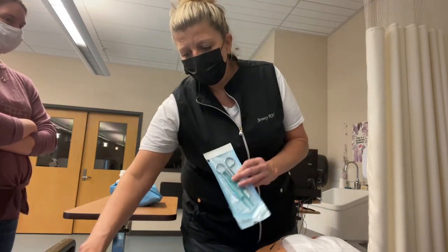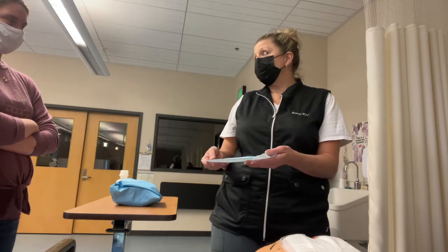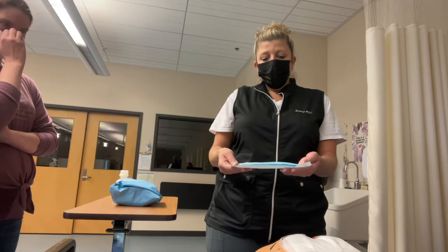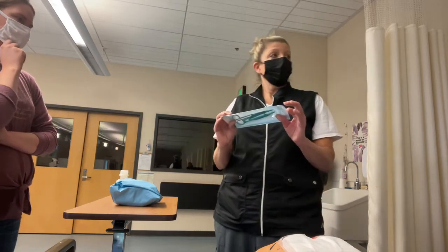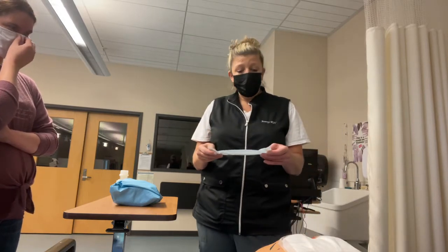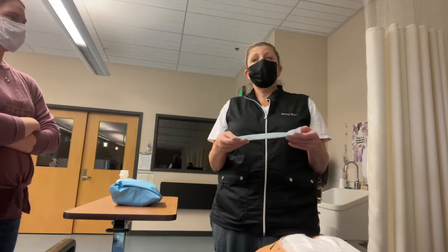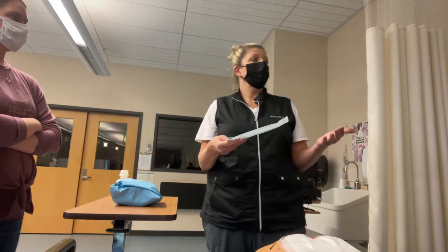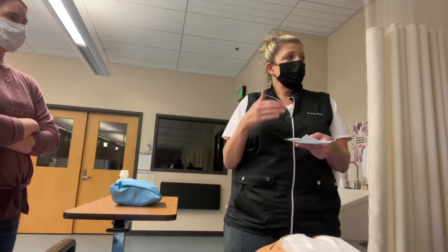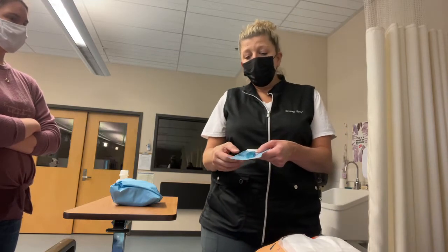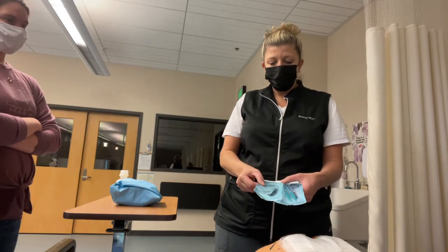So this bag is a kind of universal way that we use steam sterilization. We wrap this and then it goes through what we call an autoclave, and it sterilizes the instruments on the inside. Now, depending on the type of sterilizer that you have, it will have different parameters. With steam, it's typically time, temperature, and pressure. So once it goes through all of its parameters, things will change to tell us that it has gone through its process.